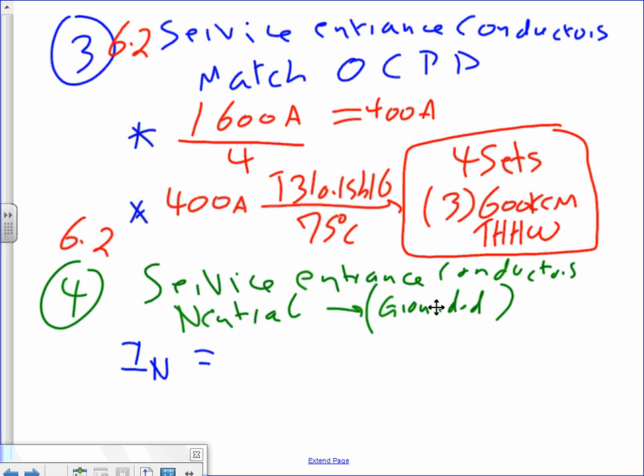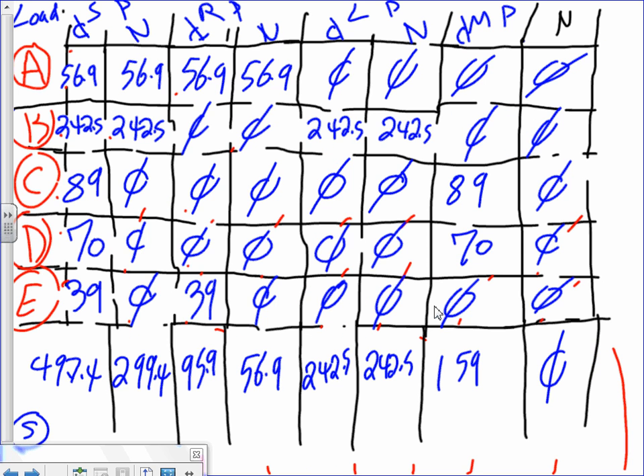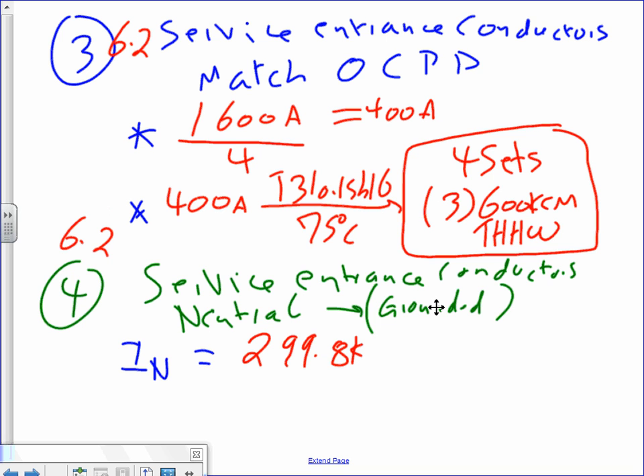Okay, what was the kVA for the neutral, gentlemen? Everybody remember? It was 299 point what? 0.8, I thought. Is it 8 or 4? I think 4. Okay. I have 0.8. So I'm right and you guys wrong. Let me see. Oh, 0.4. No, you guys are right and I'm wrong. I don't know why I have 0.8 here. So, by the way, would 0.4 kW make a difference in this calculation? Anything less than a kW, guys, a kW or less, in the size of service this is meaningless. So don't sweat it too hard. 0.4 kW. Now if you're doing control, a kW is huge. 1 kW is a huge transformer for control. For power, a kW is nothing.